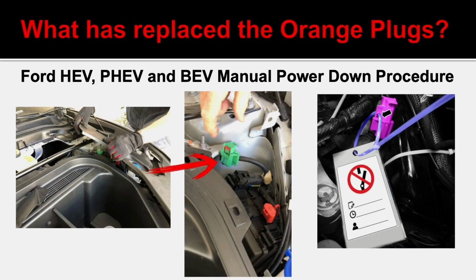There's a little green plug, low voltage, and it works on the same idea as the HVIL, high voltage interlock connection. Watch it in action. Once we get this extended, we can put a padlock in here or a lockout tag where a technician can put information on who locked it out and at what time, so we have documentation, and there's no way you can shove that back together.